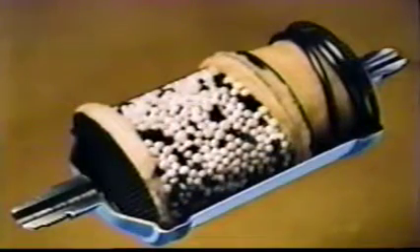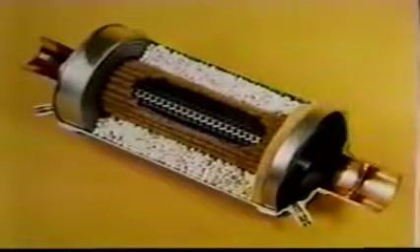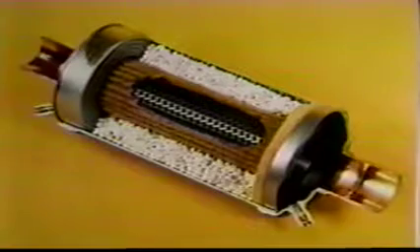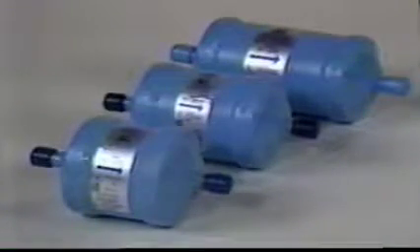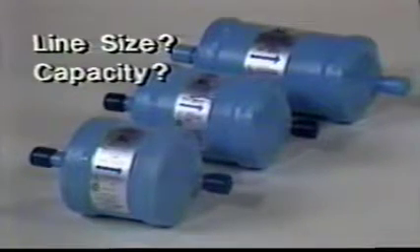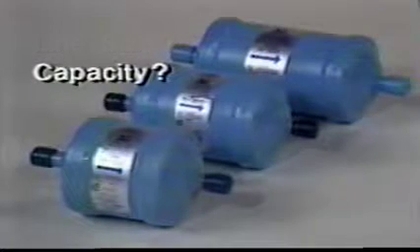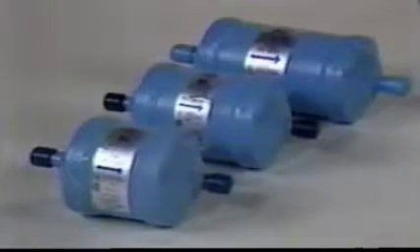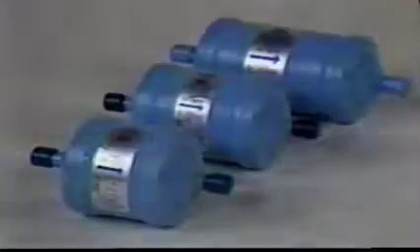Since liquid line dryers are built using a different construction than a suction line dryer, the filter dryer selected must come from a liquid line type. The selection made will depend on two requirements: line size and the physical size of the filter dryer itself. It must be understood that, like any other component in a refrigerant circuit, a filter dryer must have adequate rating to match the capacity of the system. That's not quite as easy as it sounds.